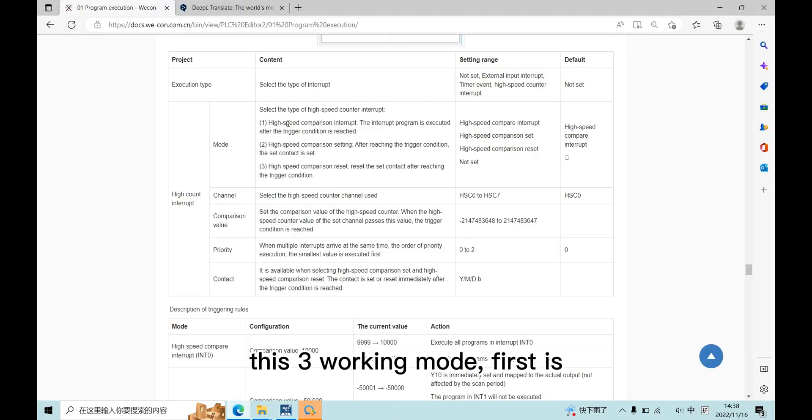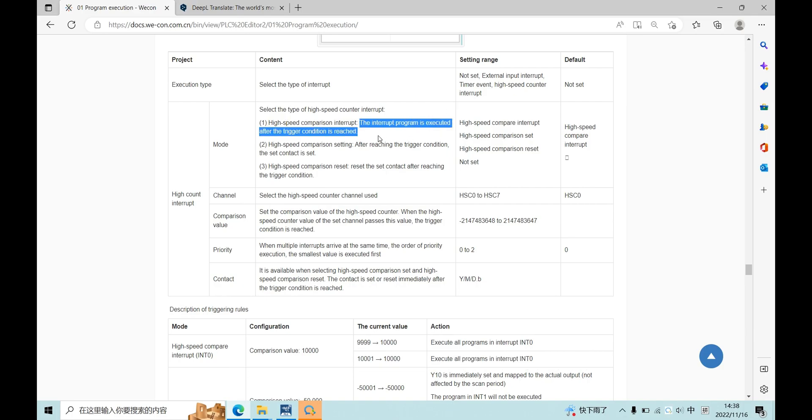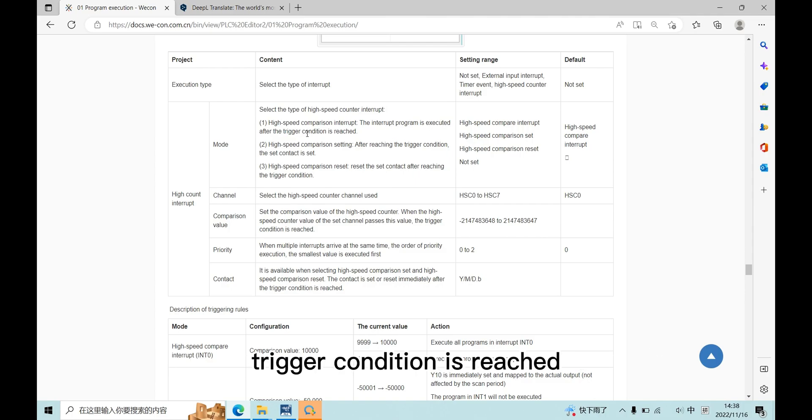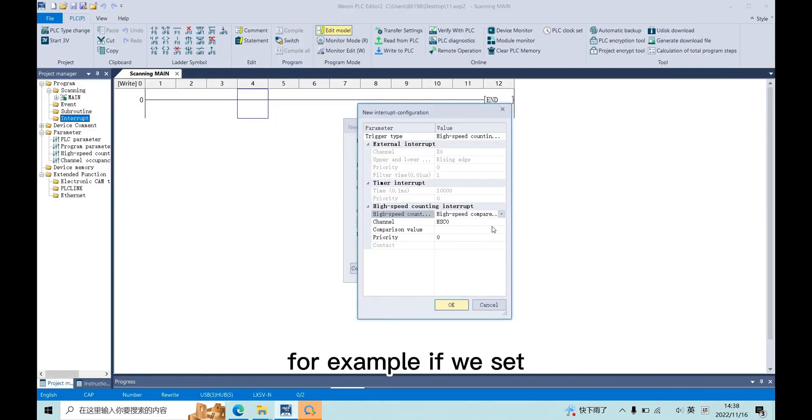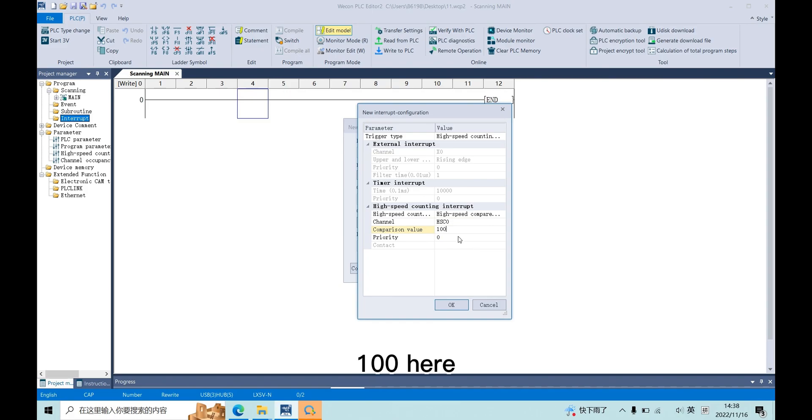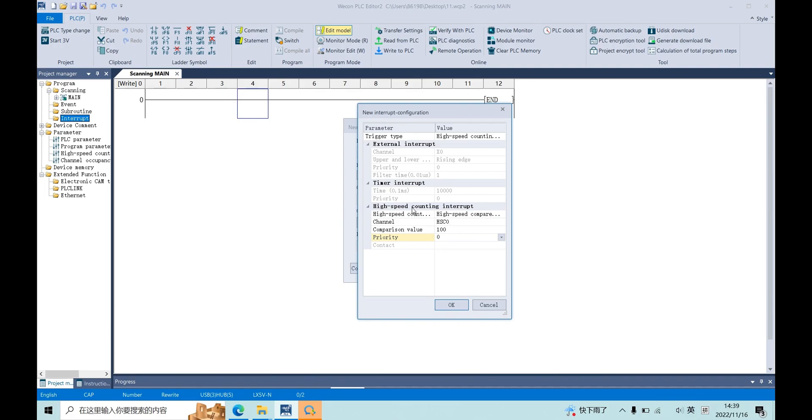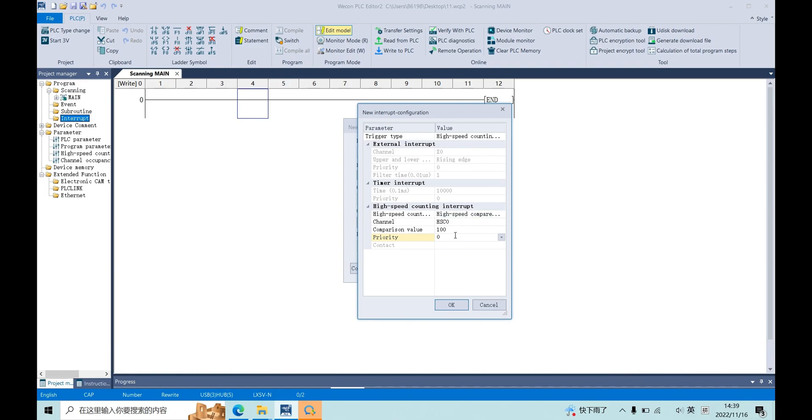First is high-speed comparison interrupt. The interrupt program will be executed after the trigger condition is reached. For example, if we set 100 here, during the program execution, when the value of HSC0 reached 100, then this PLC will begin to execute this interrupt program.